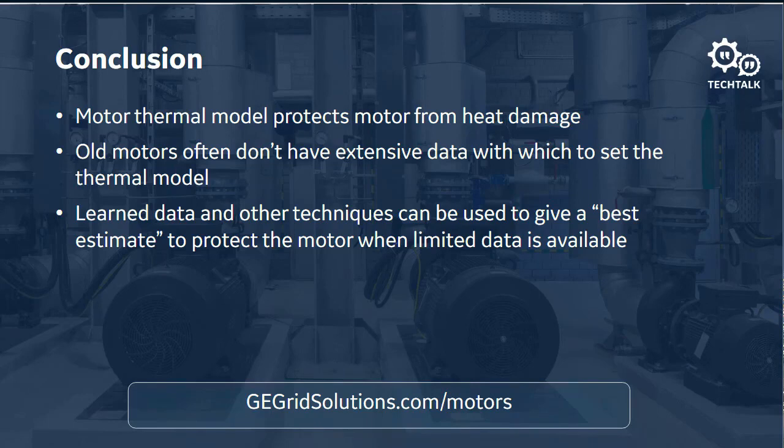In the scenario that we've discussed today, where we have very limited data and I'm making so many assumptions already, I don't know that I would want to go to the full 125% that I could if my service factor was 1.15.